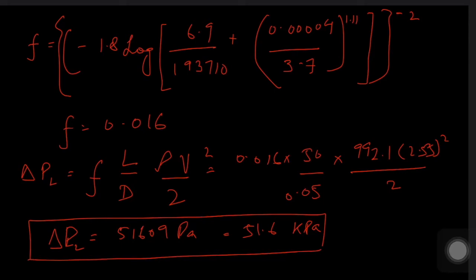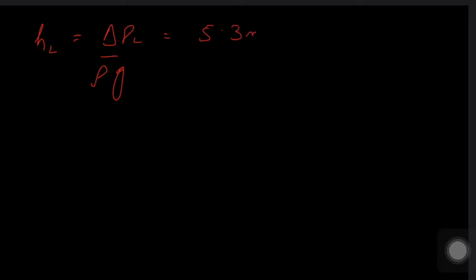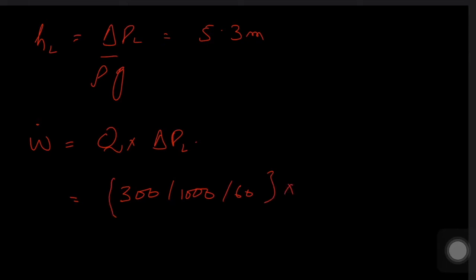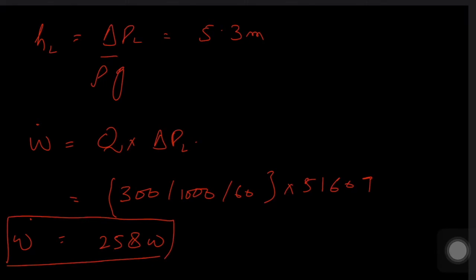Now we calculate the head loss: h_L = ΔP_L / (ρg) = 5.3 meters. Finally, the pumping power is W_dot = Q × ΔP_L = (300/1000/60) × 51,609 ≈ 258 watts. That is the answer for Example 1.